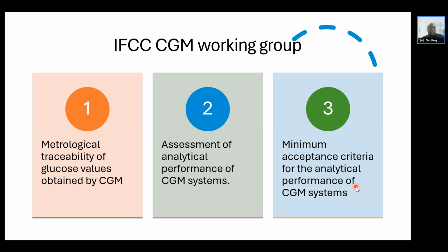It certainly is not exactly the same as a blood glucose meter, given the frequency of measurements. A CGM can actually measure blood glucose every 5 minutes. And so what performance criteria would you want to assess?